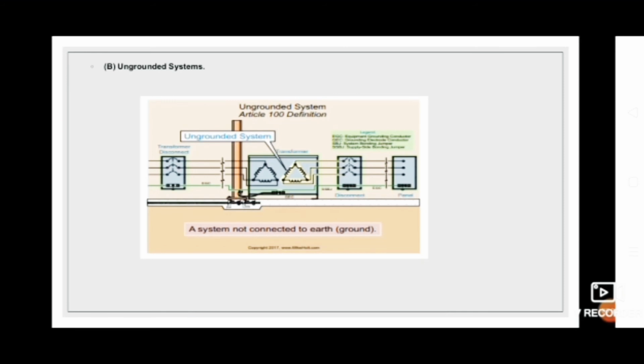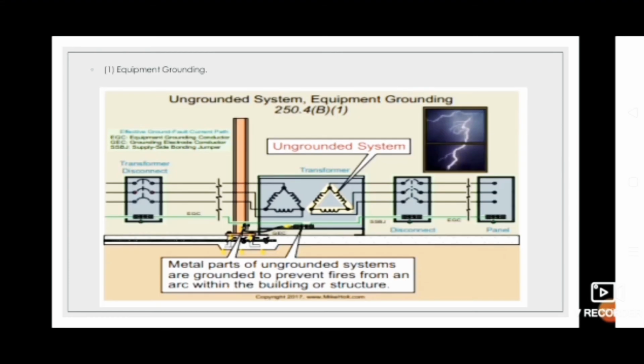And this is an ungrounded system. Ungrounded systems are those systems with no connection to the ground or to a conductive body that extends the ground connection. For equipment grounding, metal parts of electrical equipment are grounded, connected to the earth, to reduce induced voltage on the metal parts from lightning, so as to prevent fire within the building.